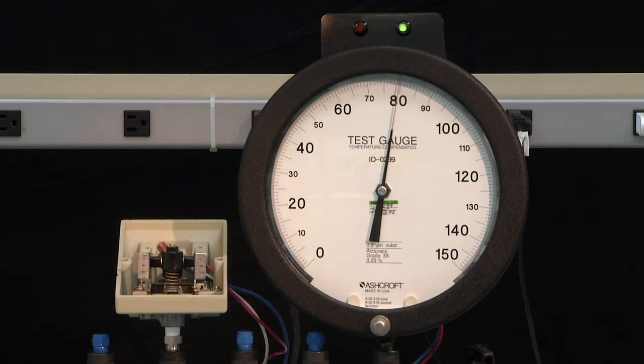Now we will lower the pressure to 0 and measure the set point to see if we have it exact. If it's not exact, we will make a fine adjustment and set it to be exactly at 80. We always start at zero. We'll bring the pressure up to just before 80 and then slow it down and get to the exact set point.